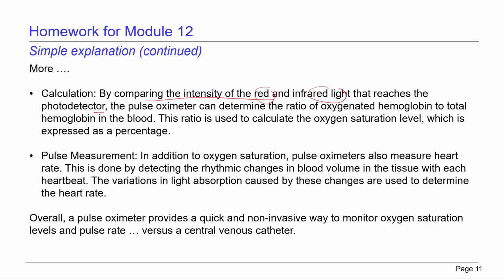Okay? So the pulse oximeter determines the ratio of oxygenated hemoglobin to the total hemoglobin in the blood. And that ratio, again, so we're going to have a ratio of ratios here in a minute, we'll see, is used to calculate the oxygen saturation level, which is expressed as a percentage. There'll also be a calibration coefficient in there, which would also have to be established.